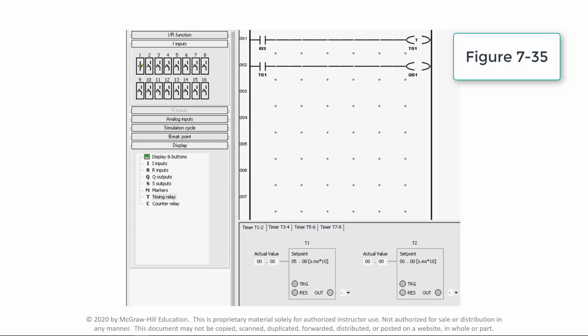When the pressure switch contacts close, the program timing output coil T1 at address T01 instruction becomes true, initiating the time delay period. After 5 seconds have passed, program timer contact T1 at address T01 becomes true, making the rung true. Output relay coil Q1 at address Q01 becomes true and energizes the pilot light.